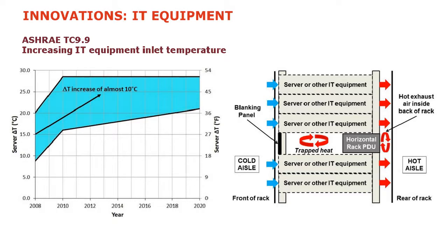So what we have to do is operate within a set of parameters that are defined by the IT manufacturers through ASHRAE. They have recommended zones, which are probably to some degree legacy. So 18 to 27 degrees Celsius is really the recommended area we should be operating in. This is the supply temperature that goes into the front of the servers, so the cool side of the server. The servers take that in, they reject heat at the back end. So historically we've always been required to supply cool air at the front of the cabinet or server between 18 to 27 degrees Celsius.